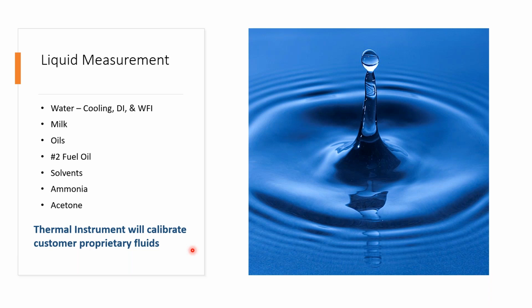You can see some of these other fluids here, like #2 fuel oil, solvents, ammonia. Different fluids have different thermal properties. As I stated earlier, we can measure up to about 10 feet per second from a velocity standpoint. Some fluids like water, yes, 10 feet per second is very doable, but maybe a thicker fluid like a #2 fuel oil, we're maybe talking 7 feet per second using our technology. That just comes down to the fact that at a certain point, it stops taking heat away from our sensor, so the flow curve tends to flatten.